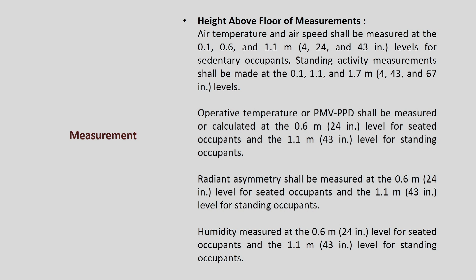At which level should we measure, like height? Air temperature or air speed shall be measured at the 0.1, 0.6 or 1.1 meter levels for sedentary occupation, if the person is in a seated condition. The same will vary if the person is standing. So, that will be 0.1, 1.1 or 1.7 meter. Operative temperature or PMV PPD shall be measured or calculated at the 0.6 meter level for seated occupants, and if standing, then at the 1.1 meter level. Radiant asymmetry, we always need to measure at 0.6 meter if seated, and if standing then 1.1 meter. Humidity also follows the same position.